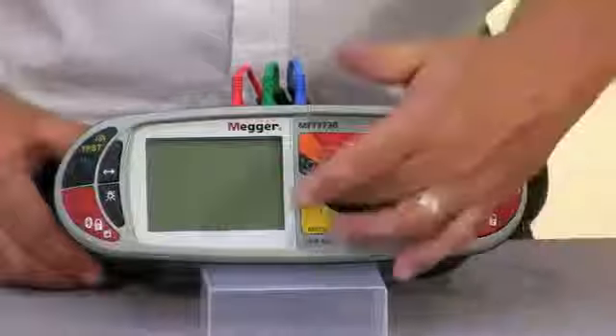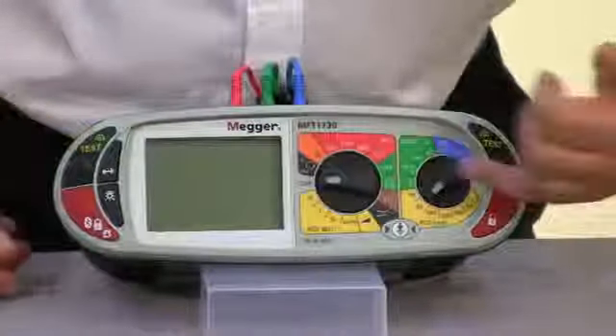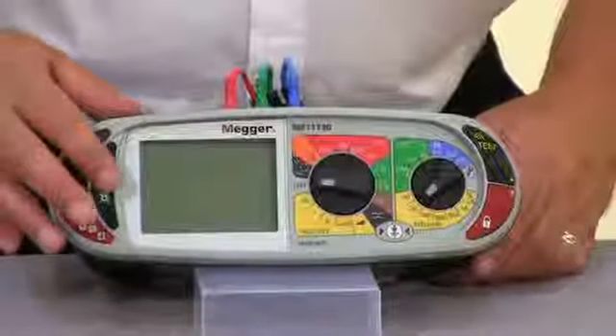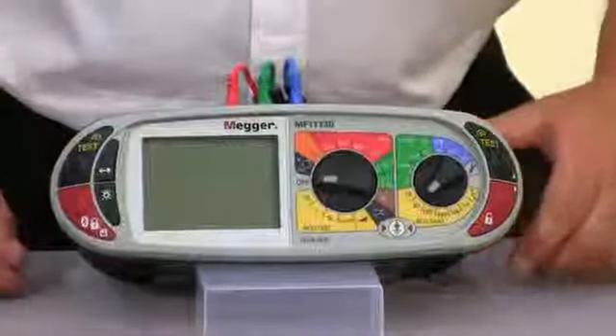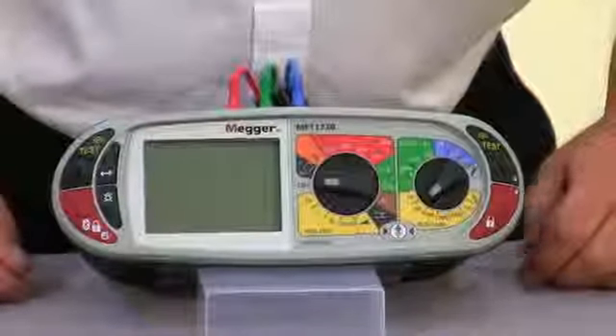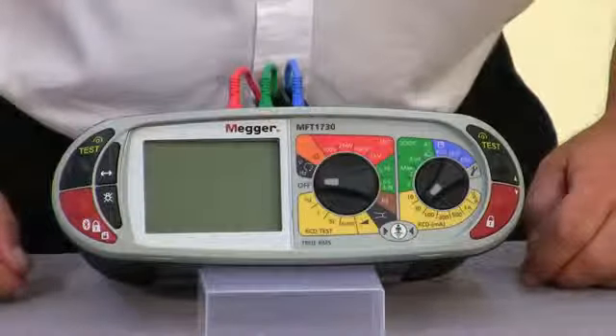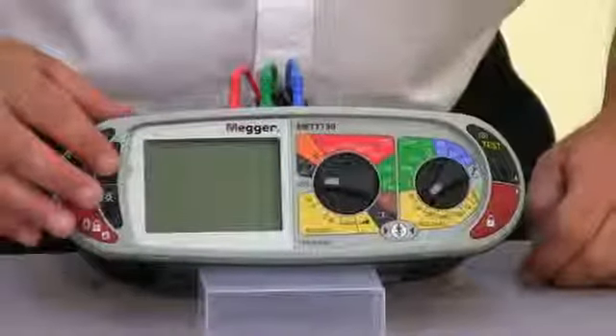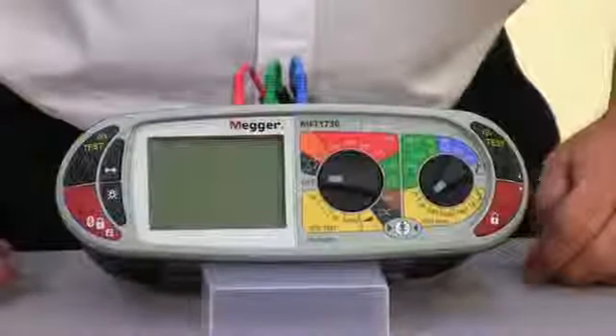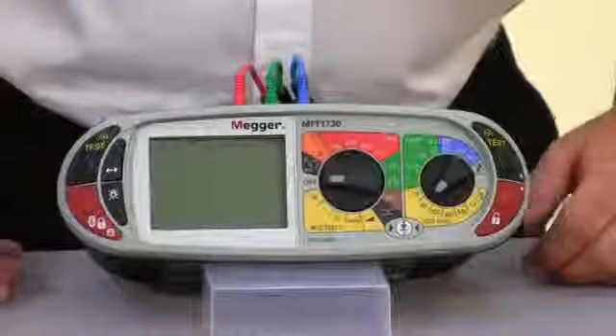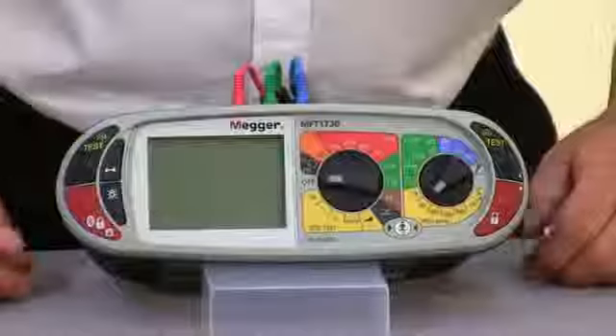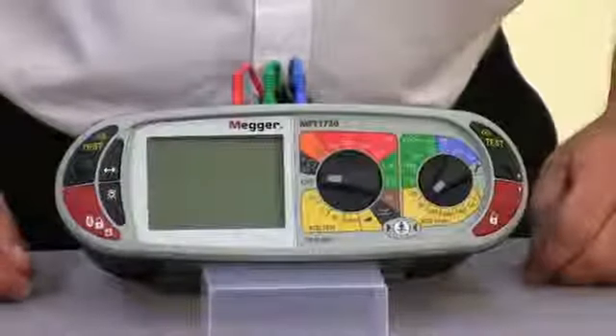Okay, so let's look at the RCD test functions. On the right hand switch, as you can see, we can select straightforward times half, times 1 and times 5, and by pressing the function key on the front we can select whether or not we're going to test on 0 or 180 degrees, either the rising or falling side of the waveform. Pressing and holding the function key will allow us to cycle through the different types of RCD, type A, type AC, selective variants of either of those, or the type B breaker.